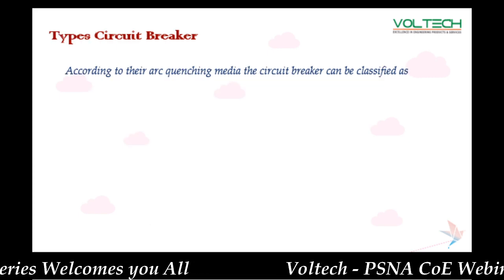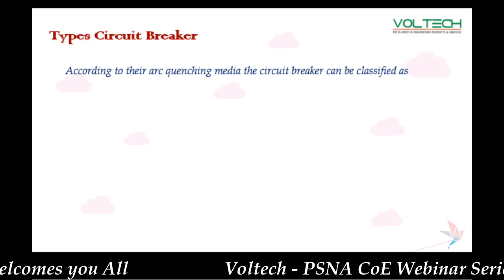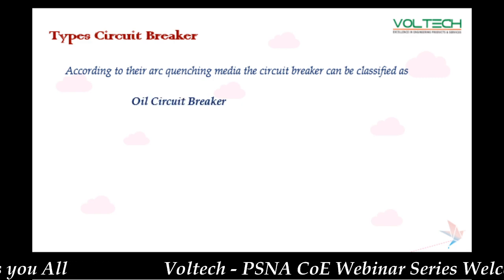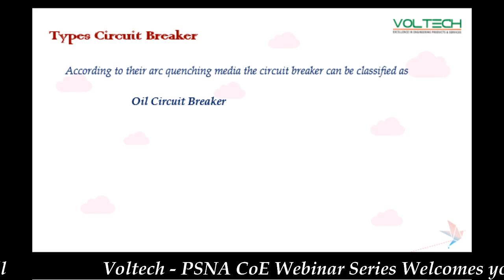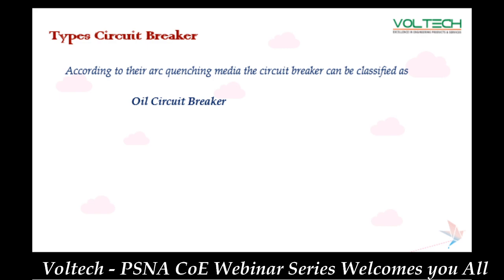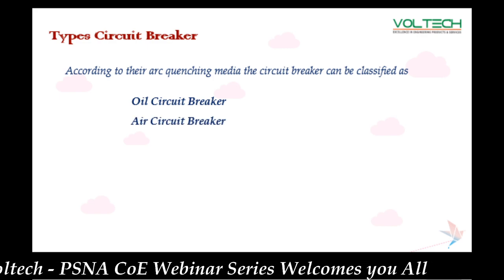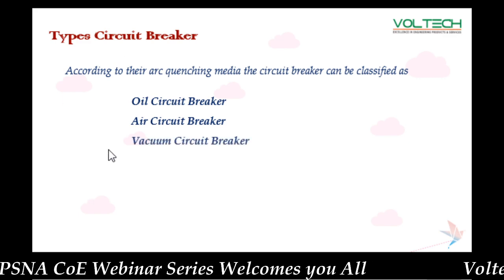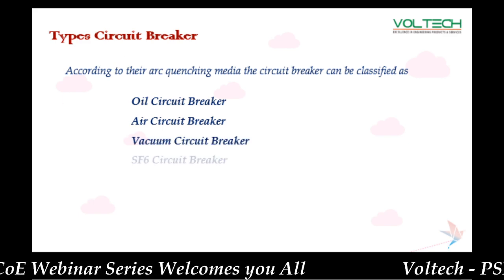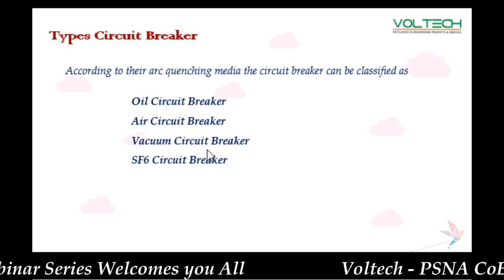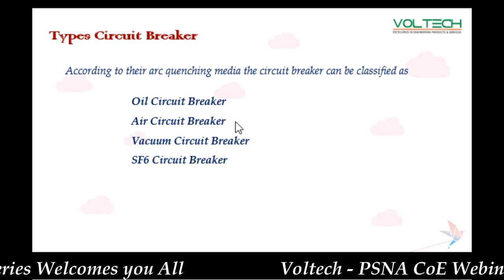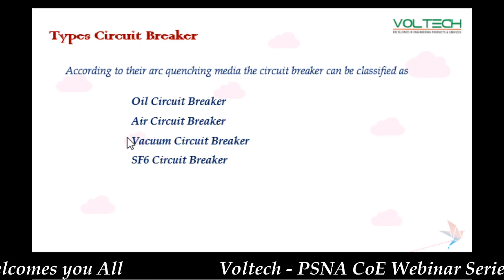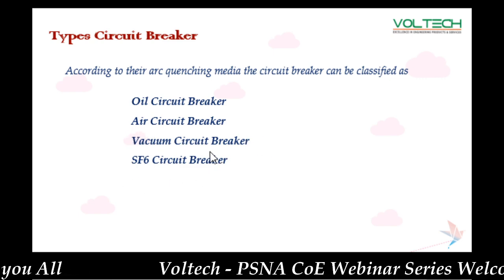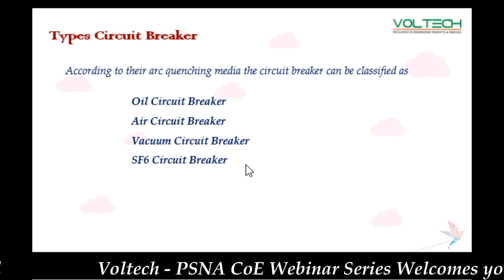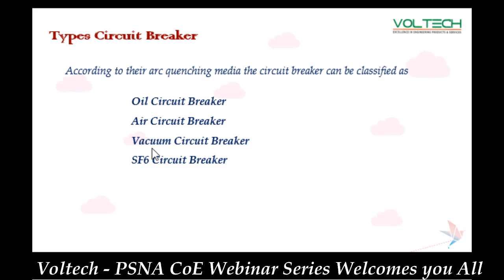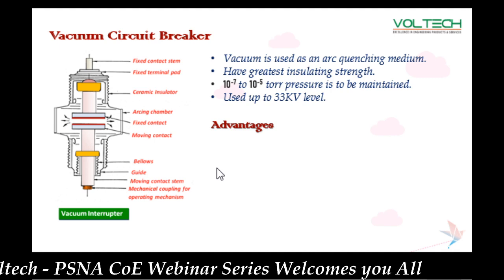So next is the types of circuit breaker. I will explain some types we are using. One is the oil circuit breaker, but nowadays we are not using any oil circuit breakers. The next one is the air circuit breaker. And this is vacuum. The air circuit breaker we mostly use on the LV side, not the HV, but vacuum we use on the MV side. SF6 we mostly use on the HV side. Some places also use it in switchgear.